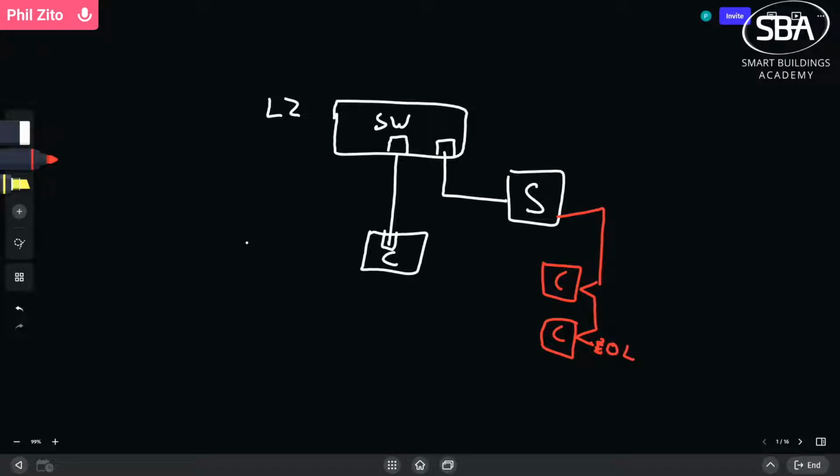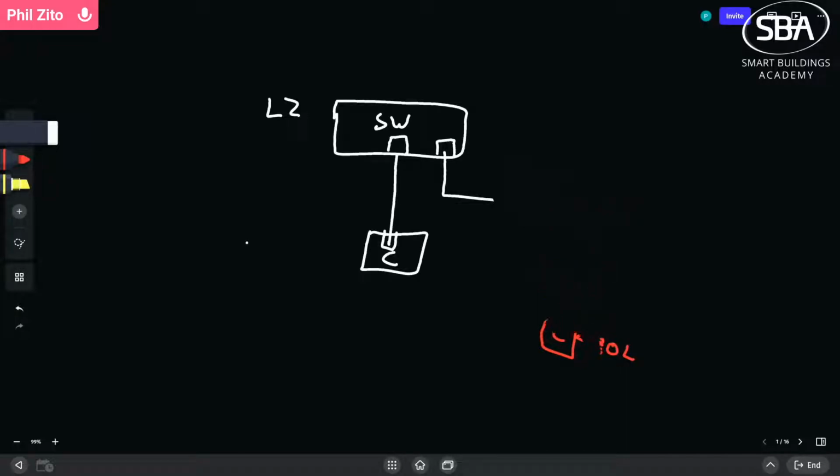Now we can make this with newer systems and newer architectures. We can actually make some changes to things here. Let me grab the eraser real quick, and I'm going to clear out this right here. Because what we can do with some of these newer architectures and newer controller lines is that some of the plant level IP controllers are actually coming with MSTP buses on the controller.